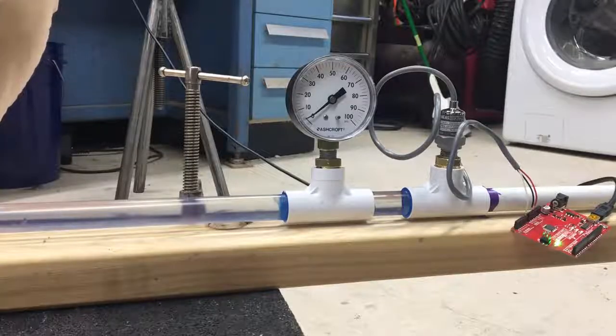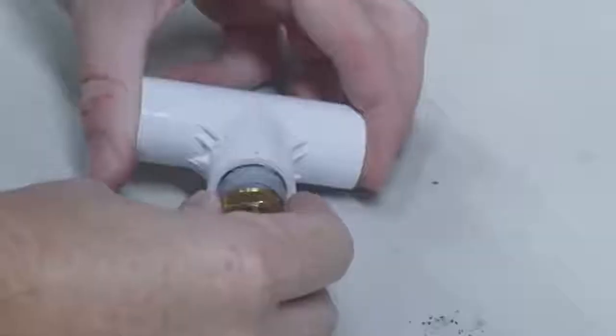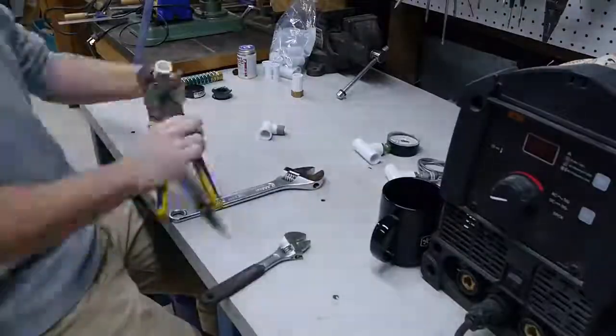That's five times the static water pressure. It's not enough to break the pipe, but way more than enough to break this pressure gauge. You can see why designing a pipeline or pipe network can be a little more complicated than it seems. These spikes in pressure can travel through a system in complicated ways, but we can use this simple demonstration to show a few ways that engineers mitigate the potential damage from water hammer.